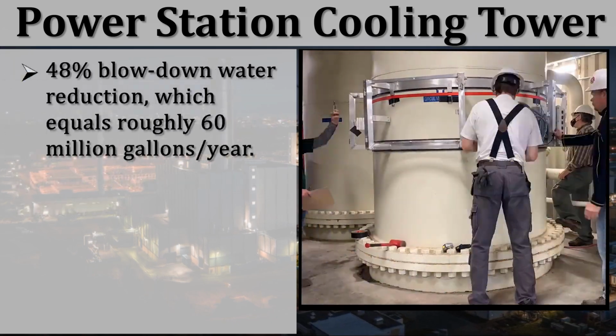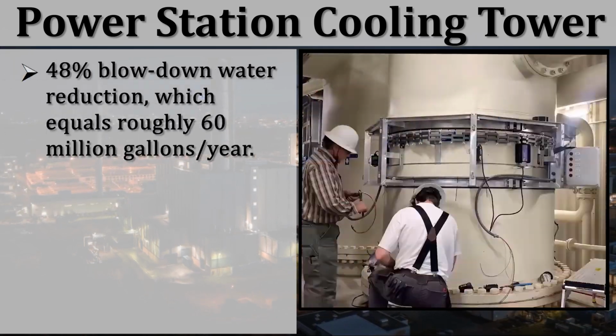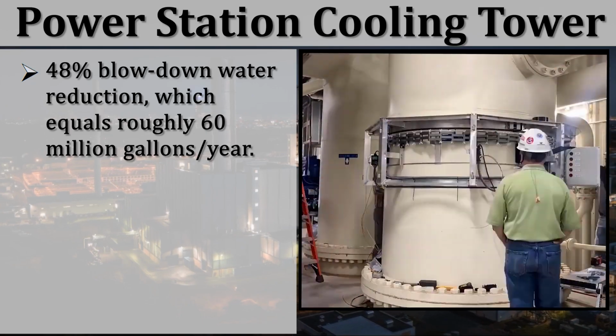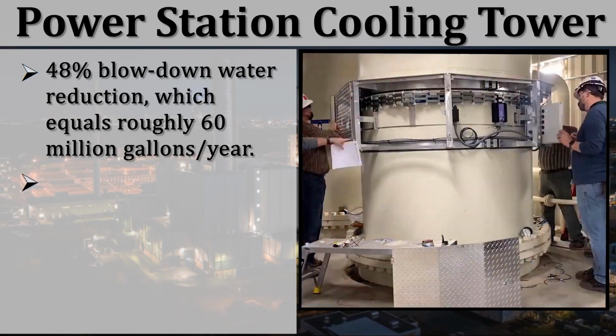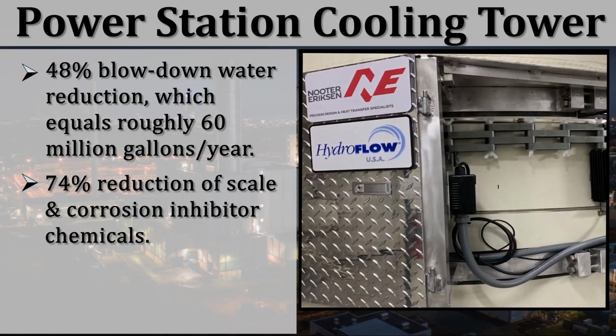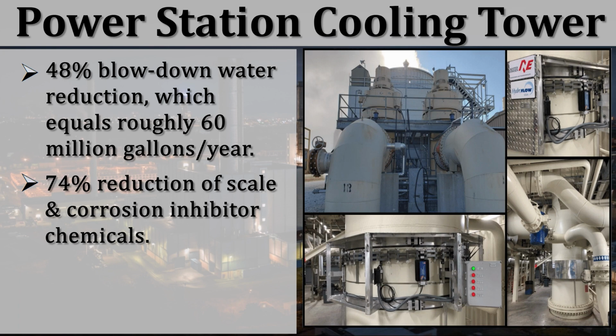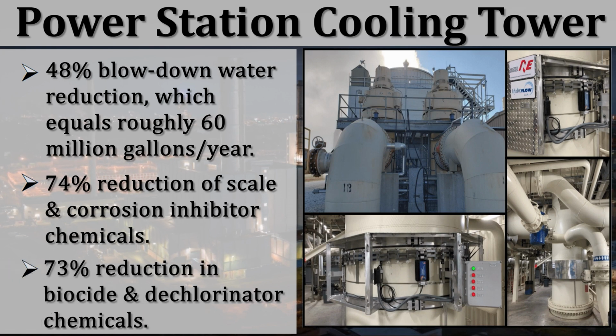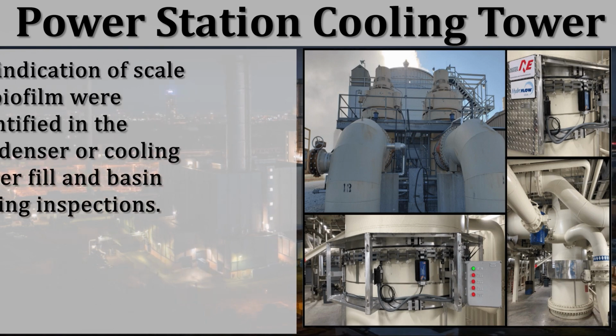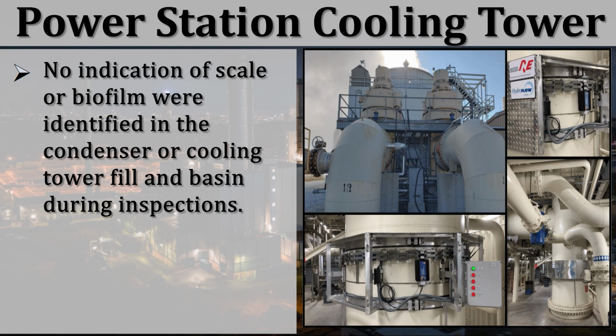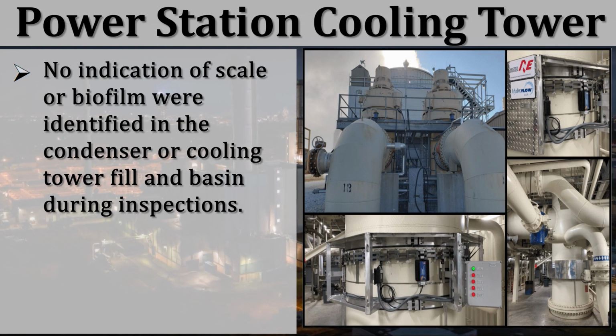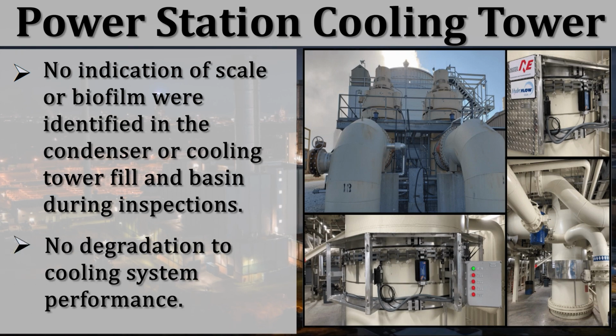Results: 48% blowdown water reduction, which equals roughly 60 million gallons per year. 74% reduction of scale and corrosion inhibitor chemicals. 73% reduction in biocide and dechlorinator chemicals. No indication of scale or biofilm were identified in condenser or cooling tower fill and basin during inspections. No degradation to cooling system performance.